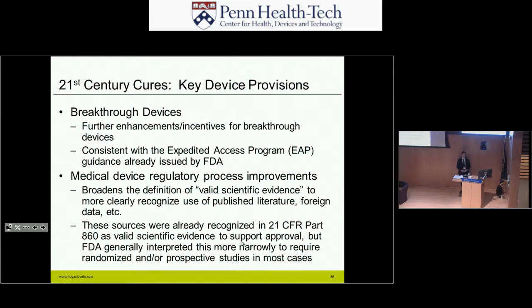Least burdensome approach, I think I mentioned this earlier, is being reinvigorated. This has actually been on the books since '97, but basically it says that FDA should not ask for more than what you need to verify that this device can be legally marketed, and should not ask for it in a more burdensome way than necessary. One interesting thing a recent guidance has put out is that when you're responding to an FDA deficiency where they say we want more bench testing, if you think it's overly burdensome, you can suggest an alternative pathway. You just have to justify that it'll get the same answer that FDA wants, to make sure that this device is safe and effective.